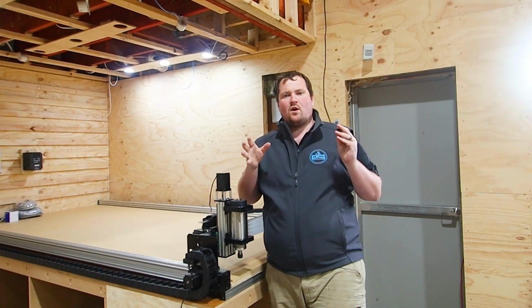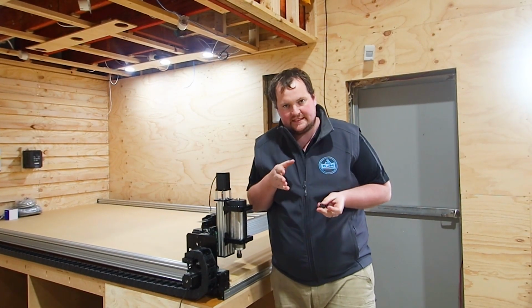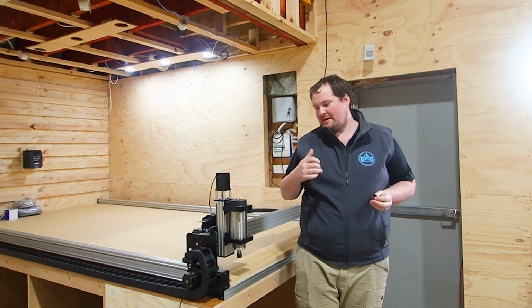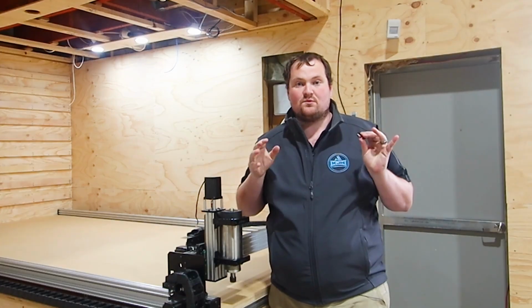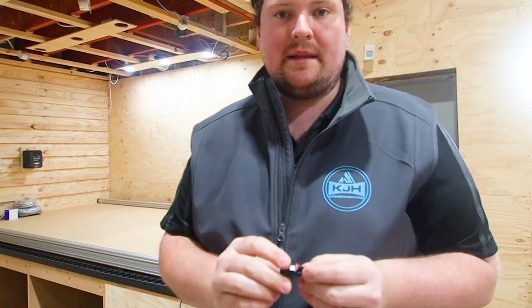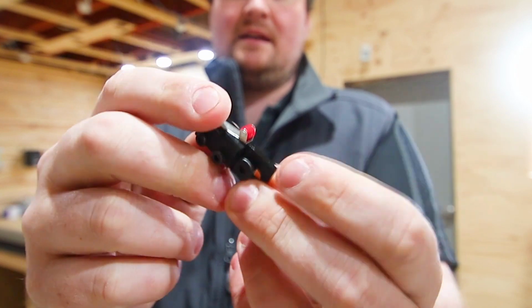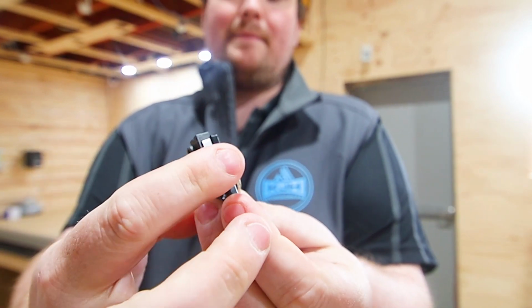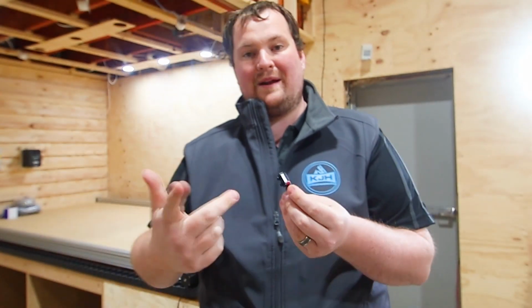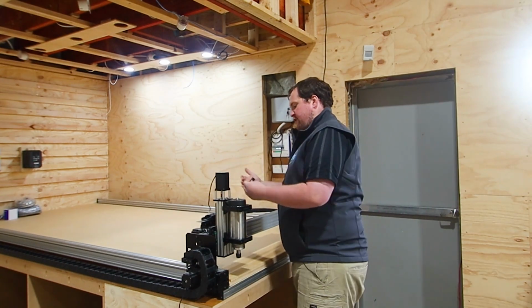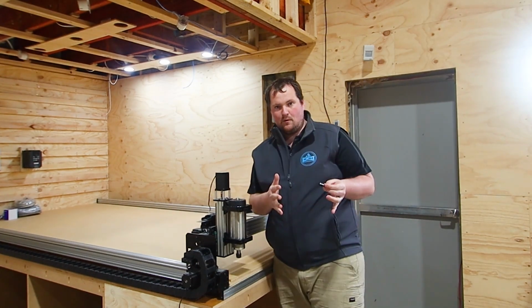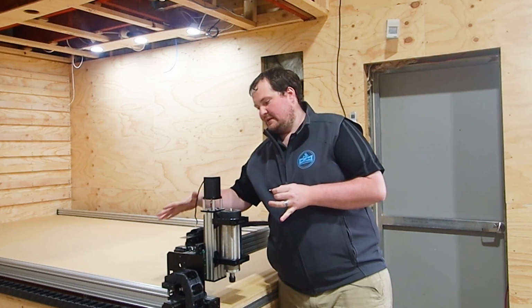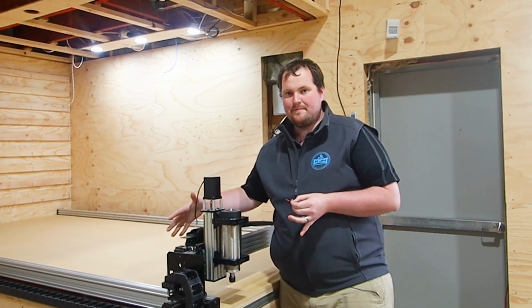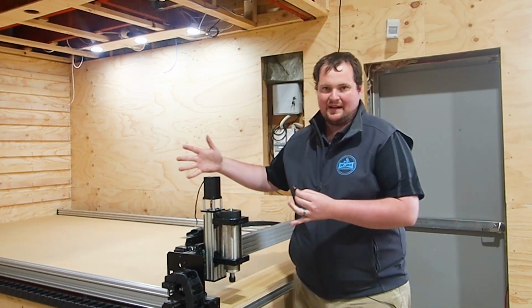The next point of call is installing your limit switches. This will be the last bit of physical hardware that goes on, and then everything else is wiring from there. A limit switch is a little device that forms a bumper which will cut the machine out when it hits it. I like to use my front left as my 0-0 point, so I'm going to install all of my limit switches in this corner—the other benefit is I don't have cables running everywhere else.